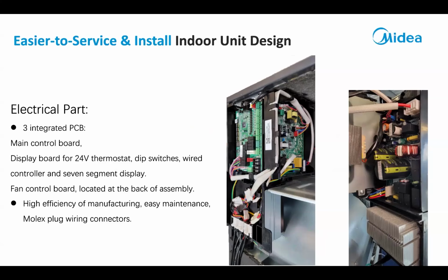You remove 3 screws, and that whole control box assembly will slide out of the air handler. The only caveat is that if you need to pull the board out very far, you will have to unplug the incoming L1, L2 plug right here. It's on the back of the fan driver board. But it's real easy to get to. It's on the top. Once you pull the assembly out, you just unplug it, and then the whole assembly comes out.